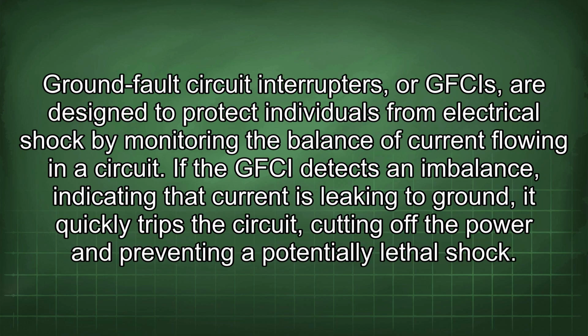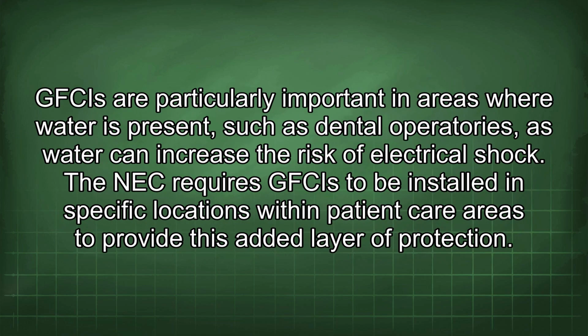Ground fault circuit interrupters, or GFCIs, are designed to protect individuals from electrical shock by monitoring the balance of current flowing in a circuit. If the GFCI detects an imbalance, indicating the current is leaking to ground, it quickly trips the circuit, cutting off the power and preventing a potentially lethal shock. GFCIs are particularly important in areas where water is present, such as dental operatories, as water can increase the risk of electrical shock.